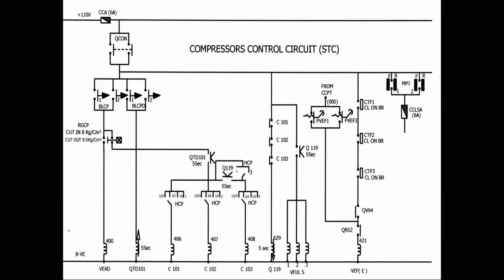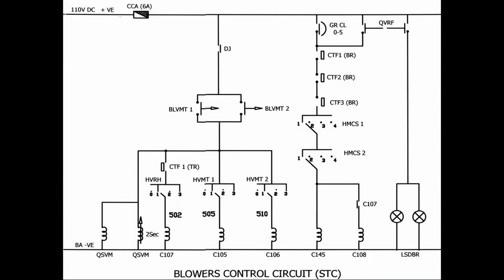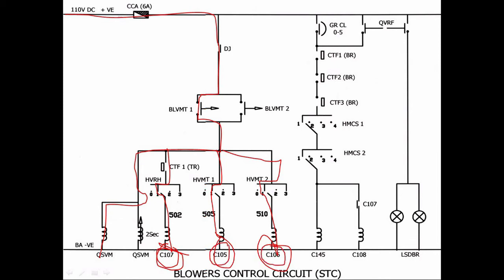Now, after closing BLVMT, when BLVMT is closed, supply from the battery charger, since DJ is already closed and the DJ normally open interlock is closed, will come like this to the relay called QSVM, and also supply will come to the C107 coil, the contactor coil. At the same time supply will come to the C106 contactor coil, and also to the C105 contactor coil. So the C107 contactor coil gets supplied, the C105 contactor coil gets supplied, the C106 contactor coil gets supplied, and QSVM also got supply.